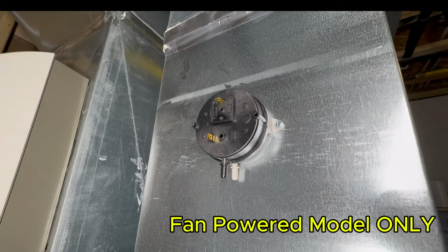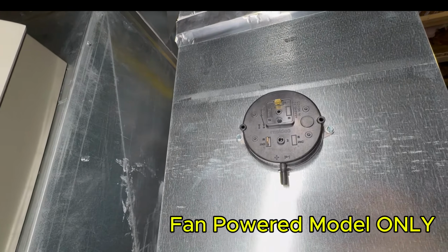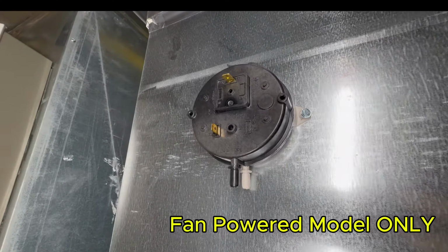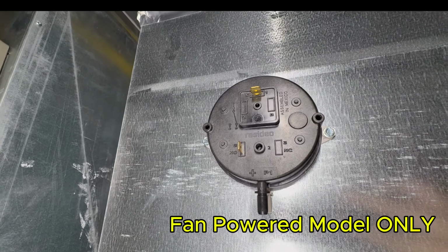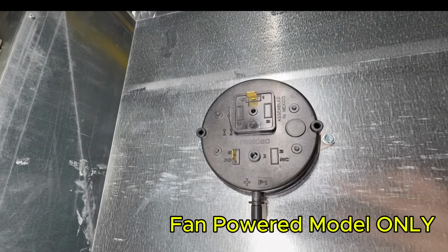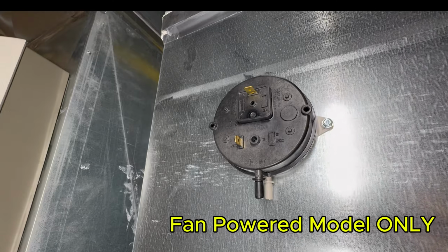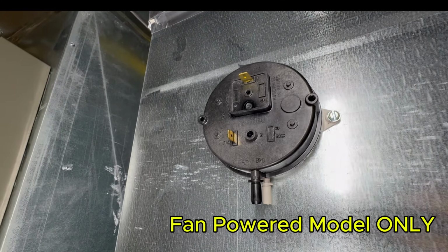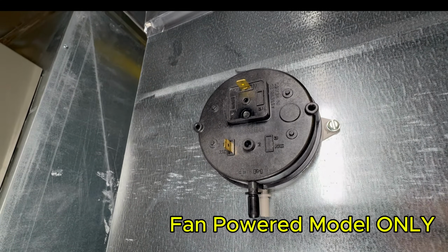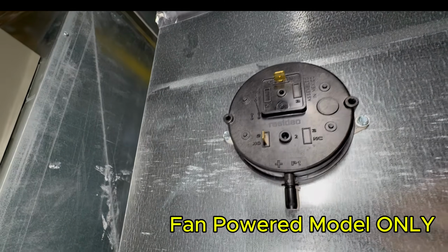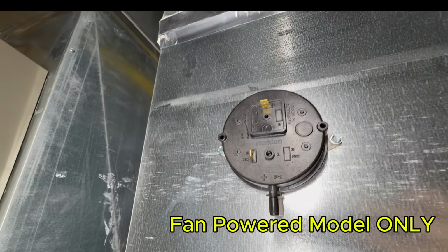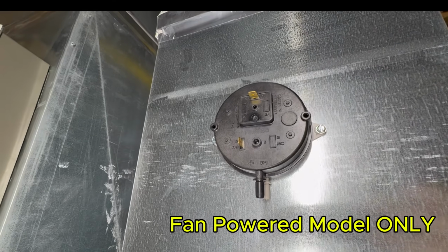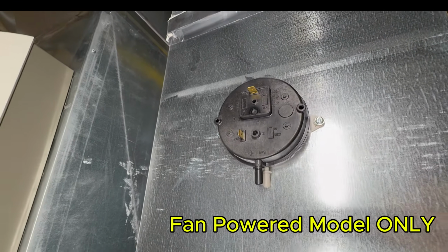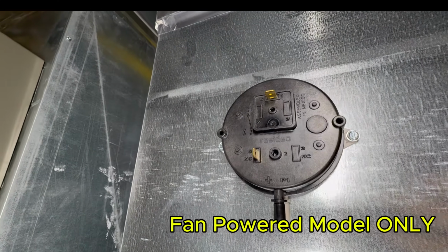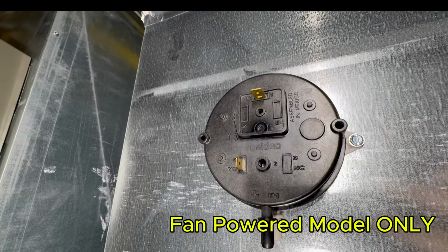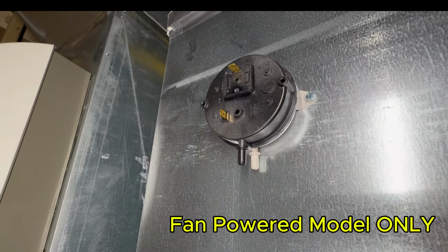Now I've got my pressure switch mounted on the return side of my ductwork, and the important thing to note here is that this pressure switch is going to allow us to complete all the connections without actually going into the furnace control board, because let's face it, if you're on here, you're not an HVAC technician. So it's better that you don't tinker with the control board. Some people will wire it directly to their furnace and bypass this pressure switch, but I recommend, if you're not an HVAC technician, use this pressure switch included in the package, and now let's wire it up.